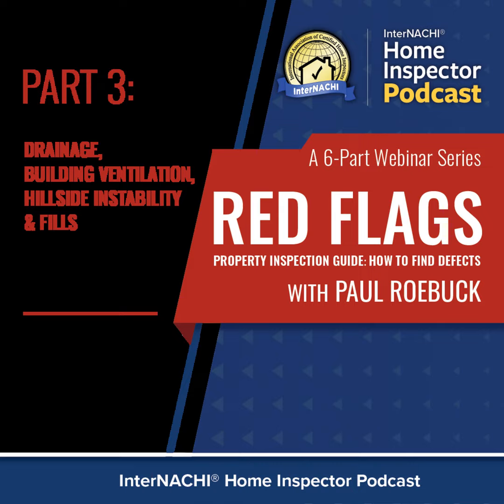Attic access. The International Residential Code, the IRC, requires attic access doors and pull-down stairs to be properly insulated and weather stripped. Today, the energy codes, the International Energy Conservation Code, require these access openings to have the same amount of R-value as the attic insulation does. So if you have an R30 or R20 requirement in your area, that insulation has to be as thick on top of that little access opening and pull-down stairs to make it meet code.